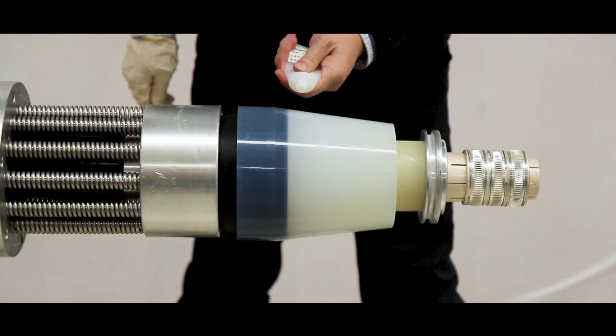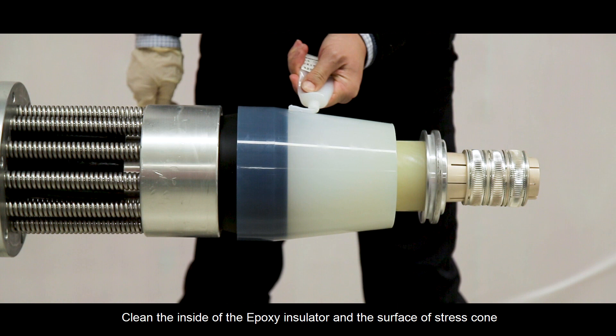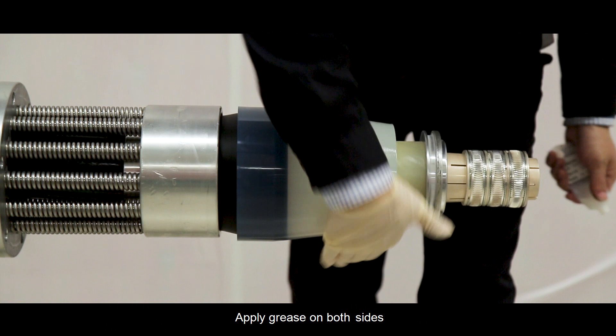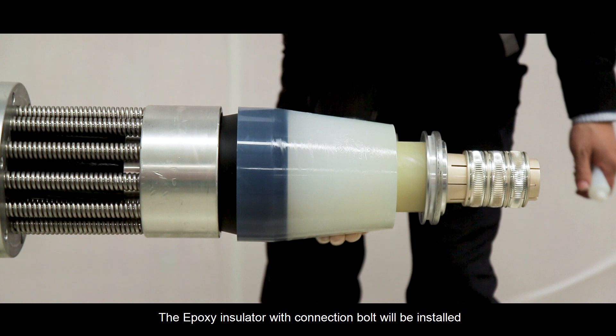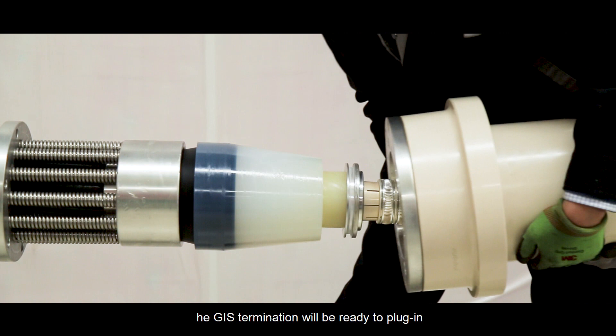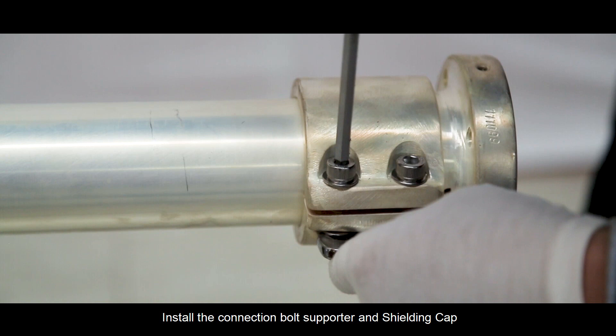Clean the inside of the epoxy insulator and the surface of stress cone. Apply grease on both sides. The epoxy insulator with connection bolt will be installed on the GIS equipment and fixed with flange. After that, the GIS termination will be ready to plug in. Install the connection bolt supporter and shielding cap. Fix them with correct nuts.